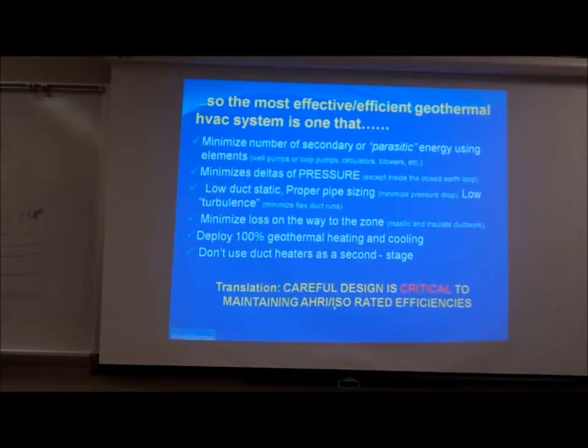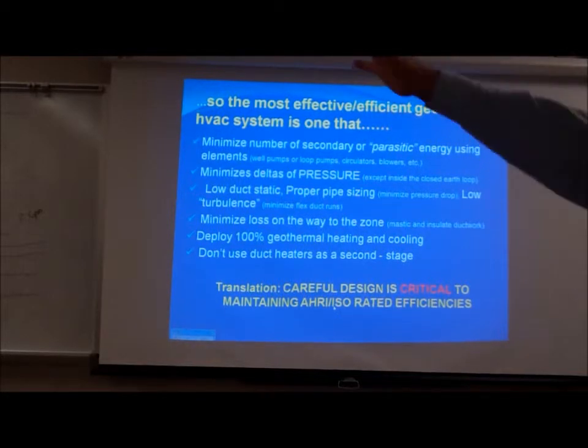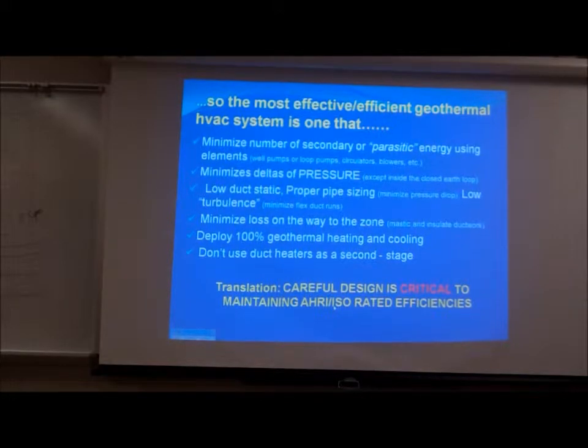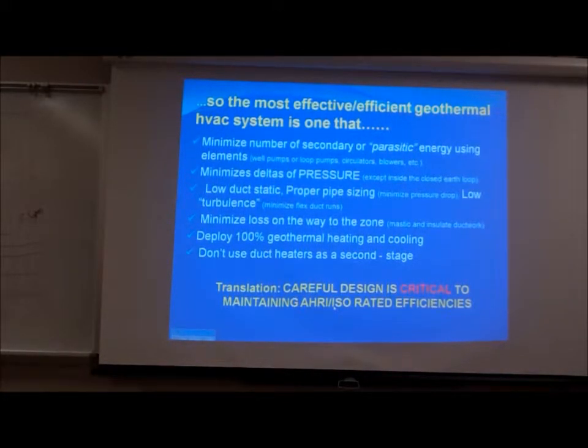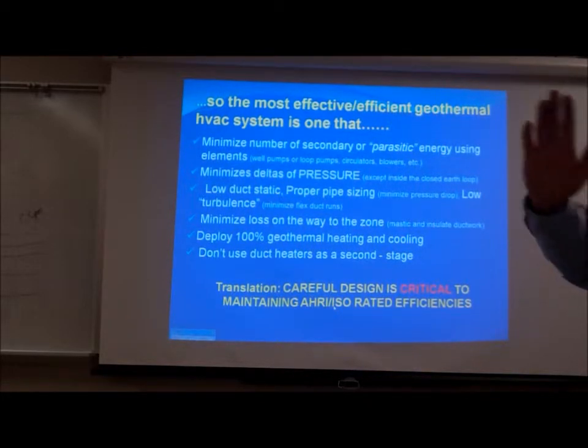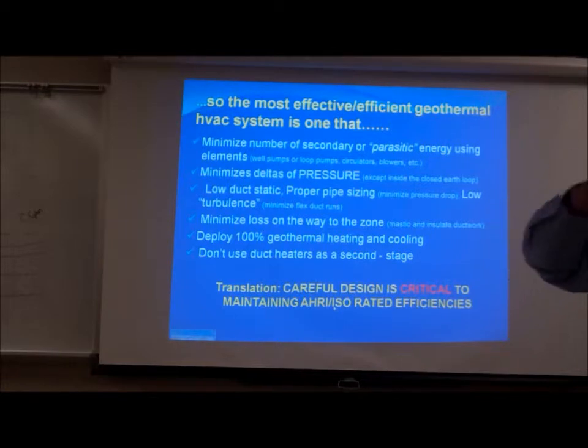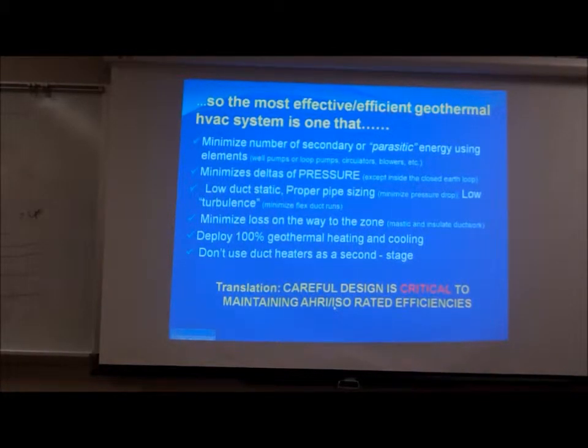Do you want a 3-year geothermal system or a 30-year geothermal system? People don't understand the importance of duct static. We want a nice, low duct static — easy breathing — because I've got a refrigerant-based delivery. Not like hot water that will just dissipate the tank temperature slower. I'm going to cook my refrigerant circuit. I'm going to take myself out of that sweet spot of psychrometric activity, either on the source or on the load side. Very important with geodesign.